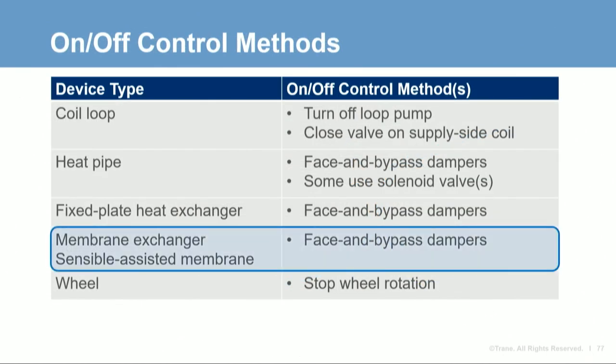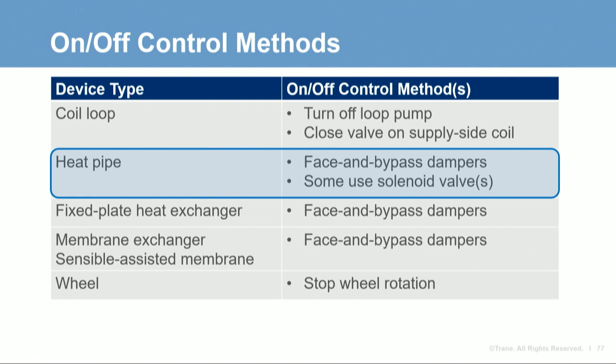Membrane exchangers aren't currently constructed with an integral bypass path, so face and bypass dampers are needed with an external bypass path around the exchanger. However, the SAM exchanger can be constructed with a bypass path through the middle. Heat pipes also use an external bypass path with face and bypass dampers, but some styles may offer solenoid valves that can prevent refrigerant from moving inside the tubes to stop heat transfer.